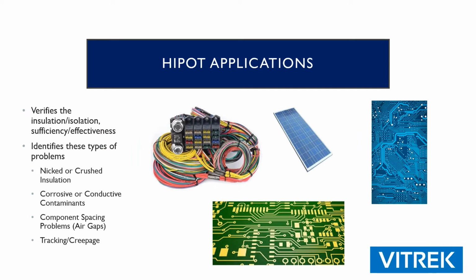So there's a variety of different applications. They all break down to basically doing the same thing, and we're measuring that isolation barrier in between 2 conductors. That could be 2 conductors in an automotive wiring harness, a printed circuit board, a cable, even a photovoltaic cell. So if you look at that schematic, they're all going to look very similar, with nodes that should be connected and nodes that should be isolated. And that's really what we're going to try to either do a no-go test on or quantify the value of some insulation there.